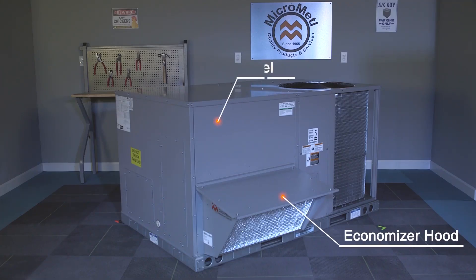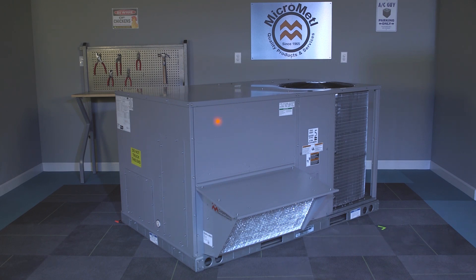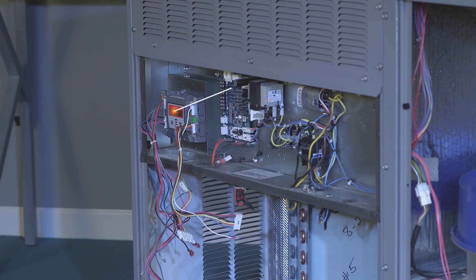Install the economizer hood and factory filter access panel. Mount the W7220 controller assembly next to the unit control board.